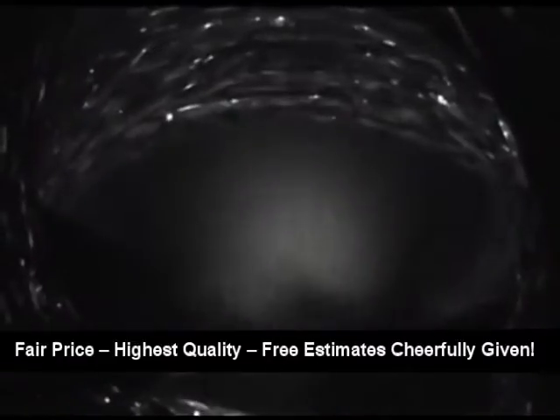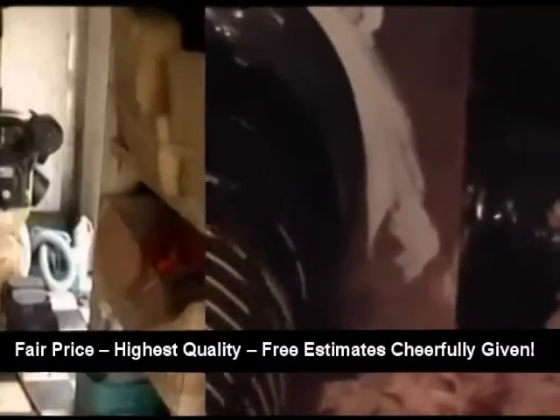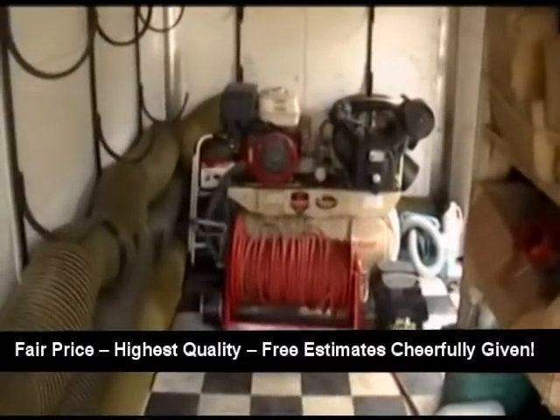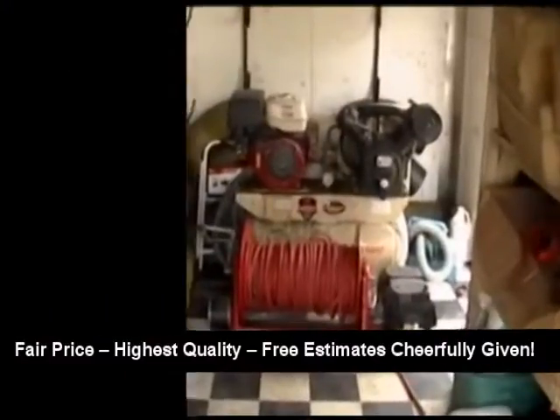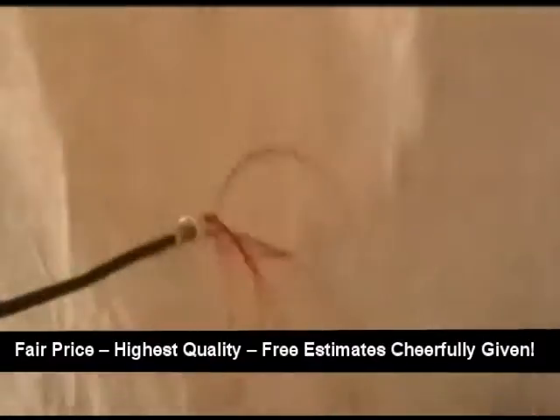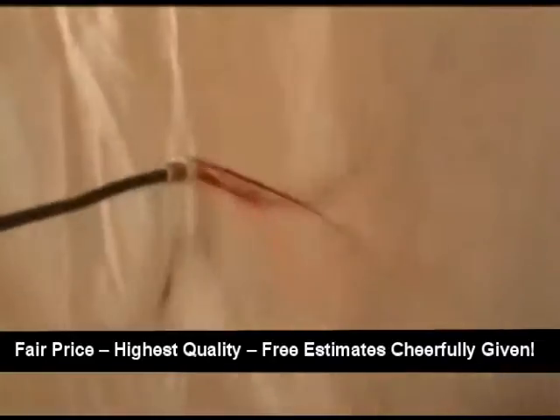What that vacuum does is it helps out in two different ways. First of all, when we start cleaning out the ductwork, nothing will ever come back inside the house because the system's under a constant negative pressure. Second of all, when we start cleaning out the ductwork, we use positive pressure. The positive pressure is 200 pounds of compressed air that's run off a truck-mounted air compressor. We have different types of agitation tools that are hooked on 1/4-inch rods that can snake up the ductwork up to 100 foot.